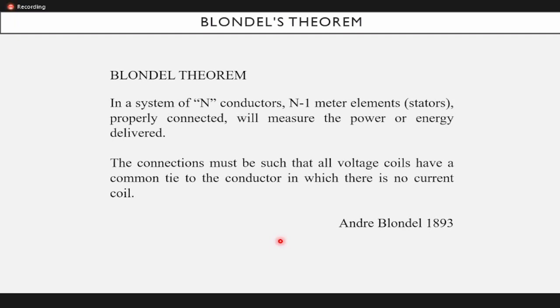From the Handbook for Electricity Metering, the theory of watt-hour metering was first set forth on a scientific basis in 1893 by French engineer and mathematician André Blondel. Blondel's theorem applies to the measurement of real power in a system of any number of wires. To simplify, in a system of n conductors, n-1 elements or stators properly connected will measure the power or energy delivered. The connections must be such that all voltage coils have a common tie to the conductor in which there is no current coil.